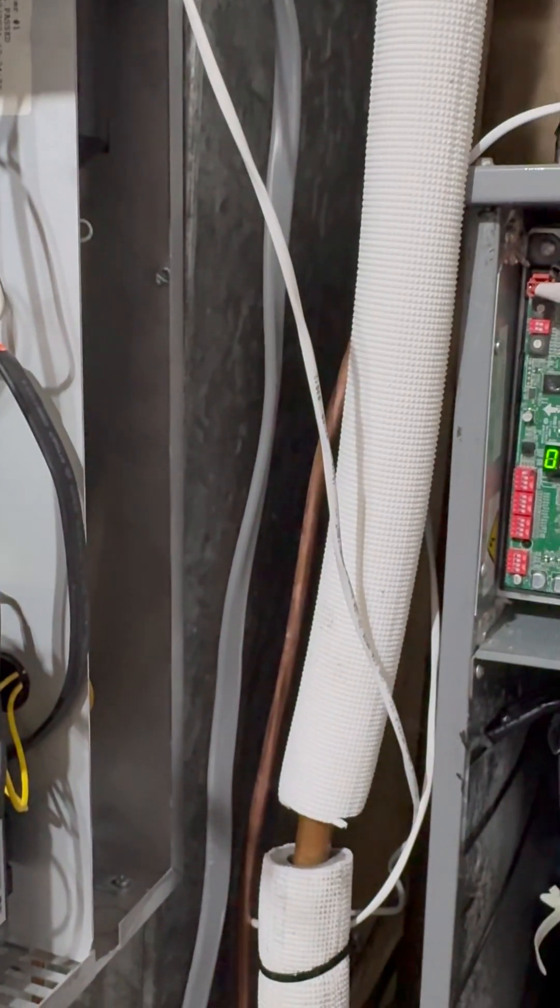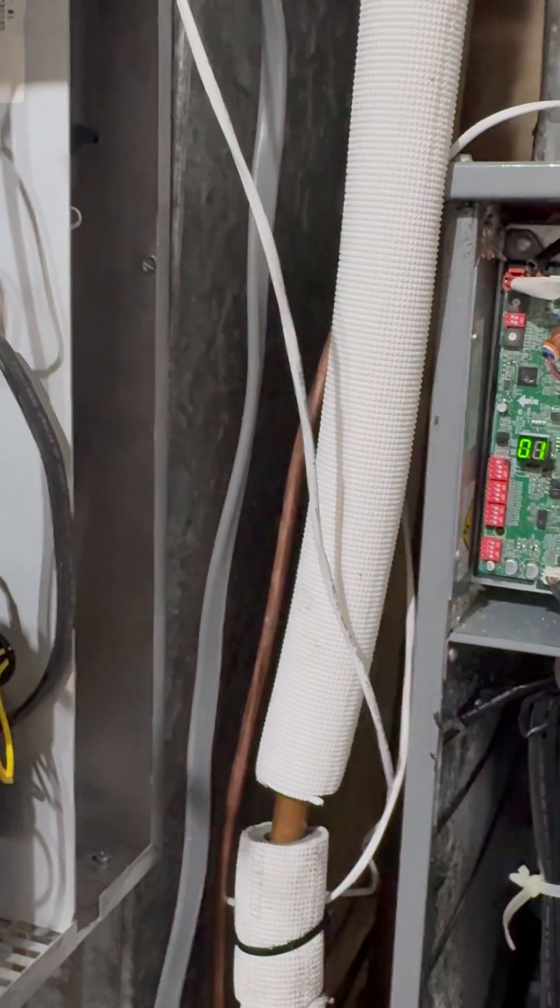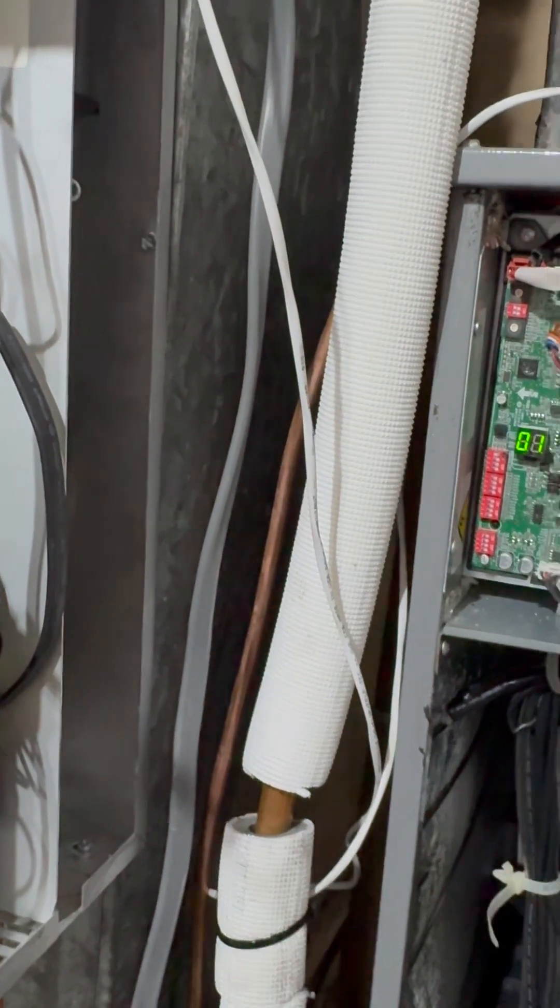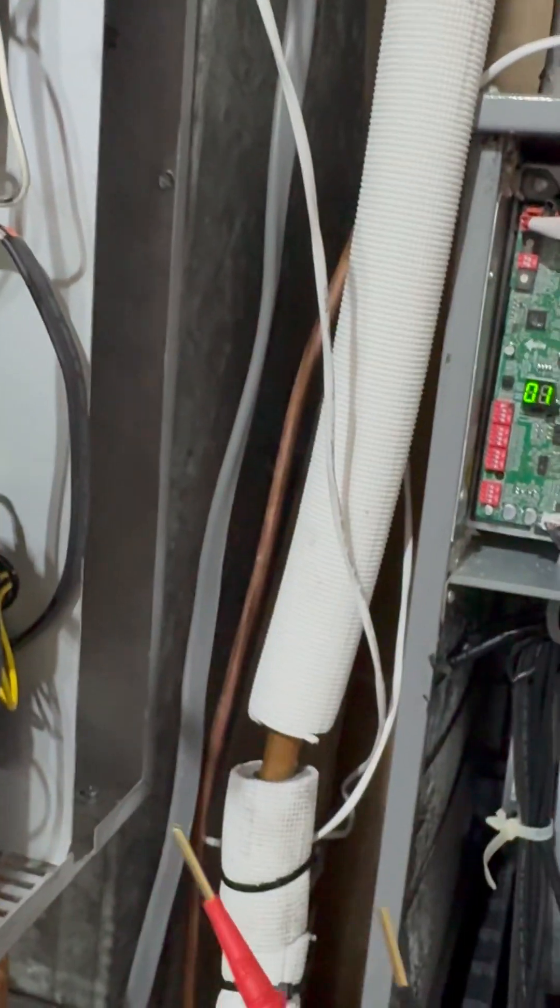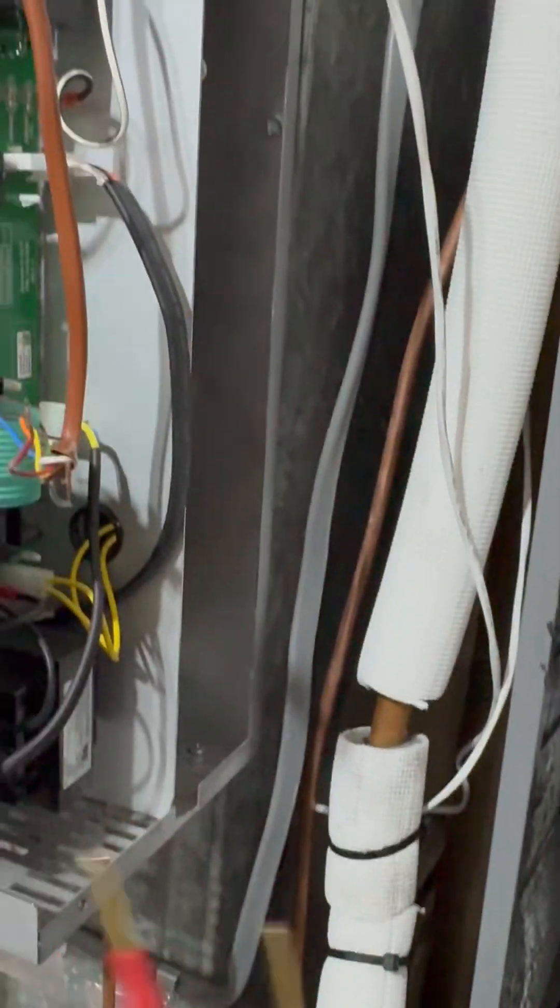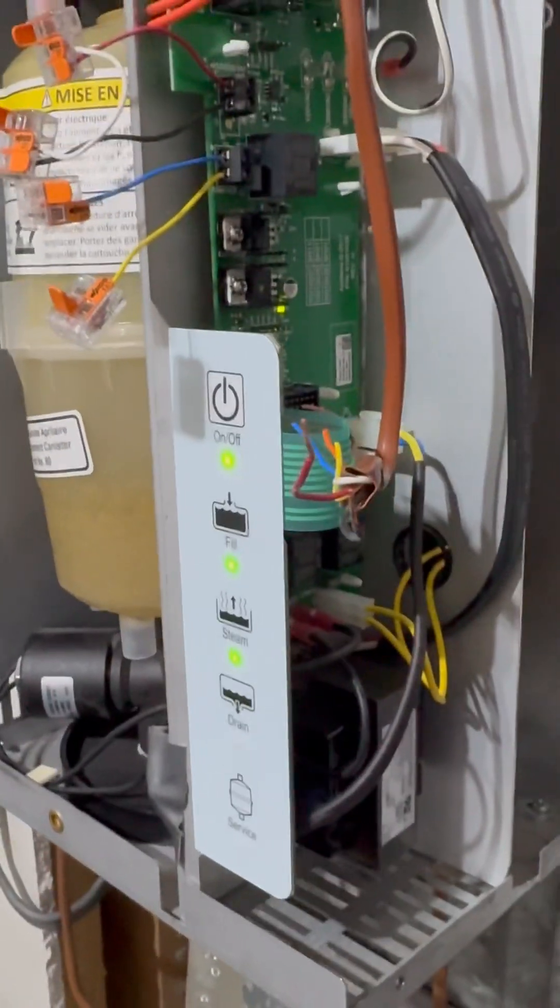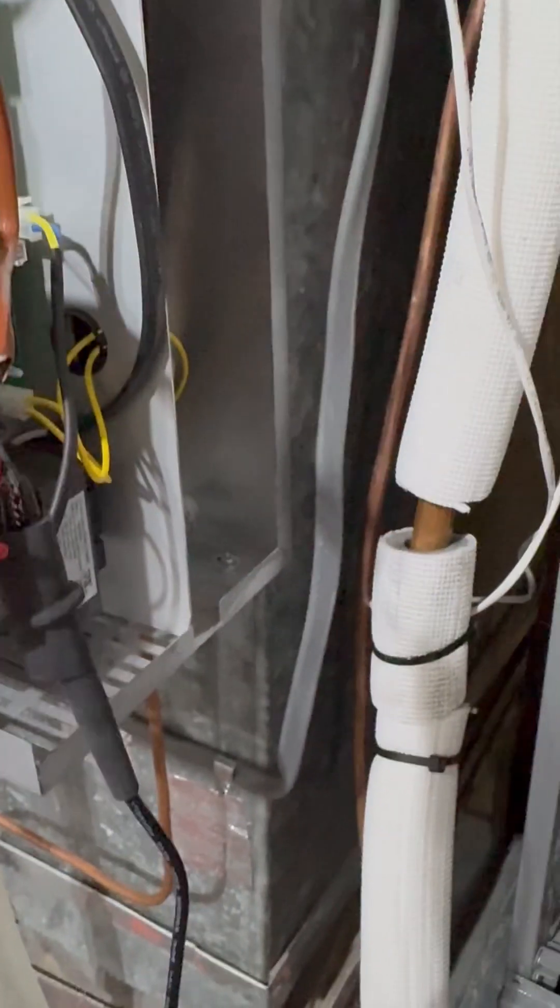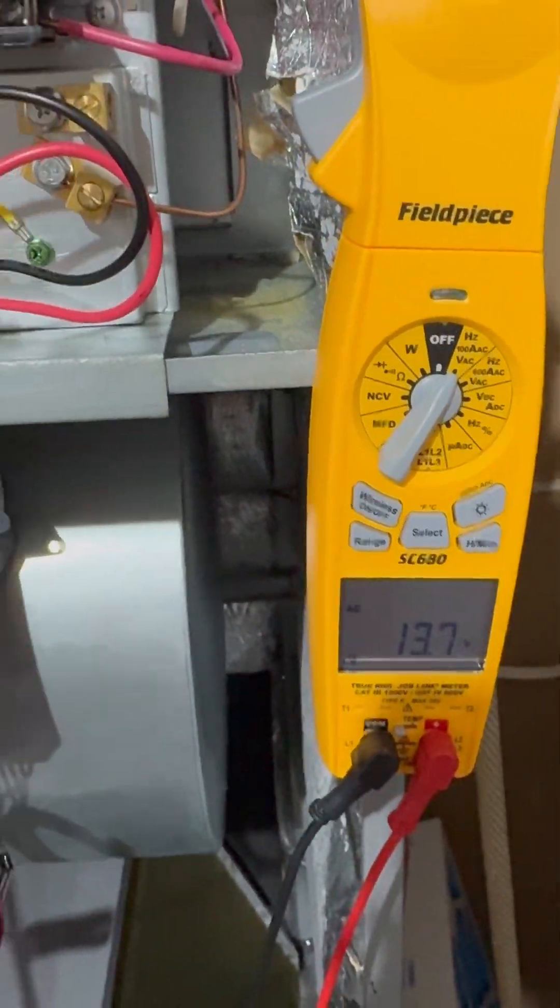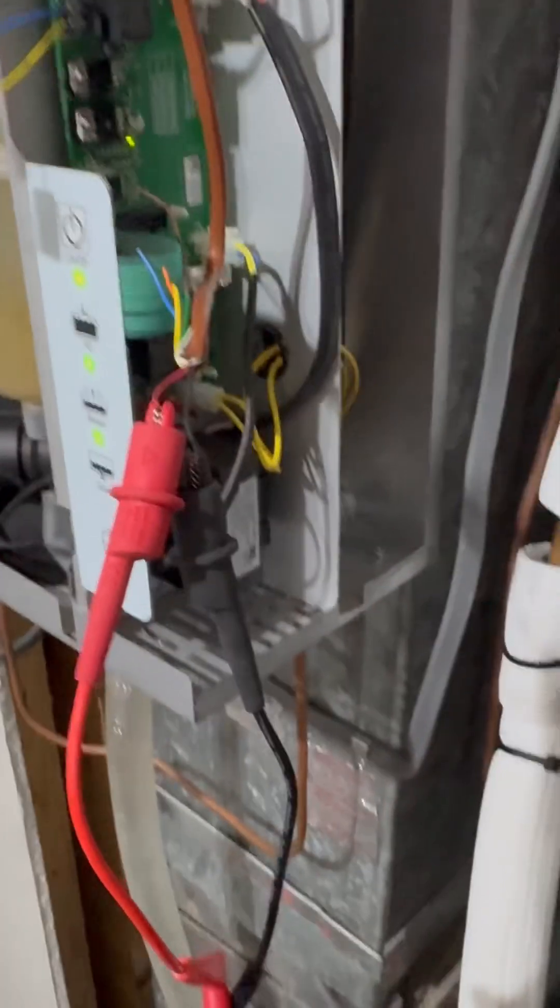That's because the Ecobee is sending a voltage signal instead of a pure dry contact on-off signal. And to help illustrate that for you, I'll go ahead and show you. Give me one moment, let me put my alligator tips. All right, so now I got my alligator tips - we're getting 13.7 volts from the Ecobee thermostat when it's calling for humidification.